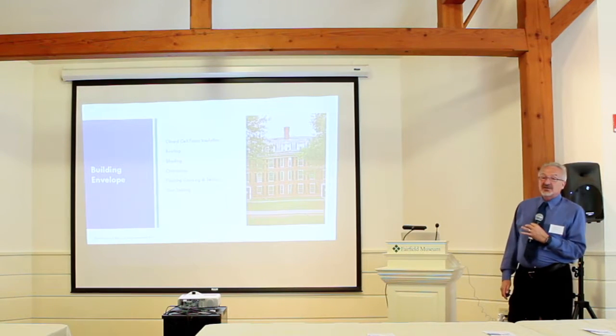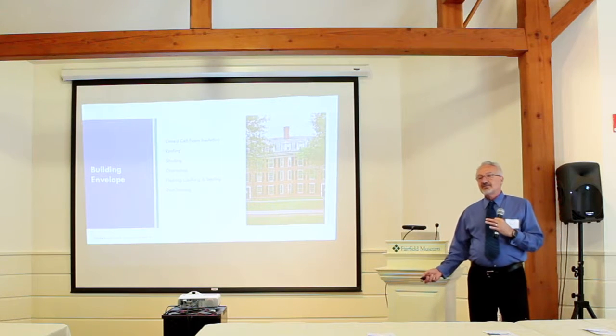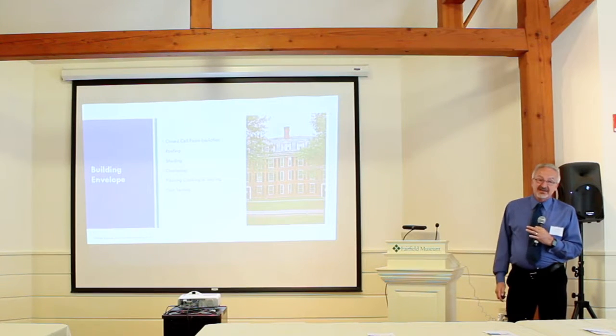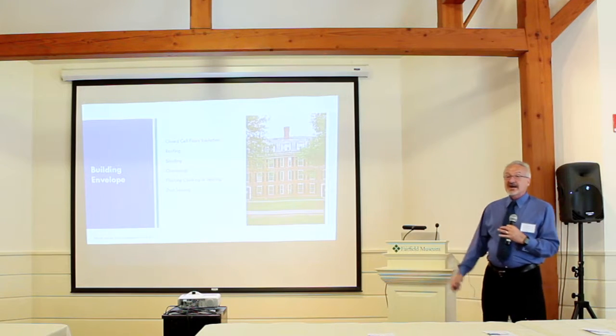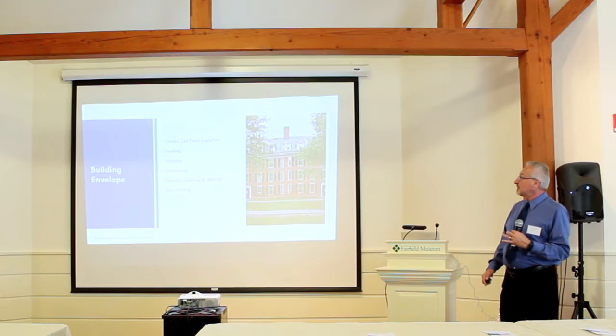You know, say, building envelopes. When we're doing a load calculation for a building, the biggest offender is ventilation and air infiltration. So, if you have high outside air requirements, you've got to look at, can I reduce my air? Can I put demand control ventilation in? What can we do?